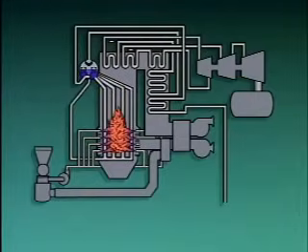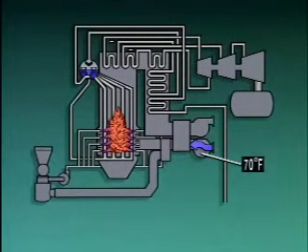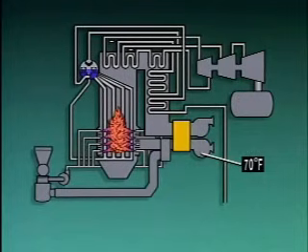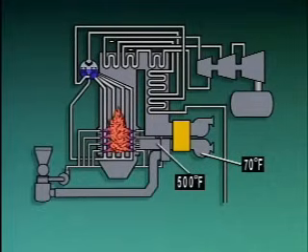Let's take a more detailed look at a typical coal-fired boiler to see how this works. Air flow starts at a forced draft fan that takes in air at atmospheric temperatures and pushes it to the boiler. In the boiler, the air passes through an air preheater where its temperature is raised to about 500 degrees Fahrenheit.